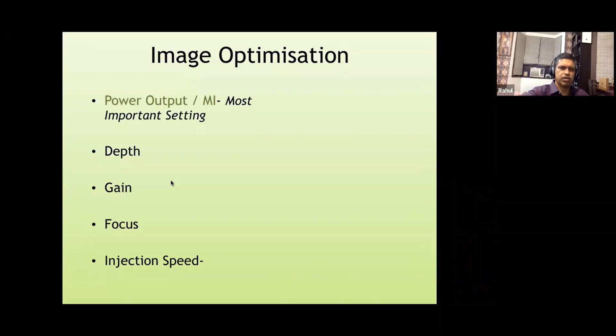If the gain is too high, like you see in this image, it will result in less differentiation, less contrast between the blood pool and the myocardium. The whole of the image is very bright. While if we have too low gain settings, we will be getting dropouts in our image, particularly the basal segments will not be so well appreciated. So depth should also be adjusted, so only the LV is in the view. We are not concerned with the LA, so we can reduce the depth accordingly.